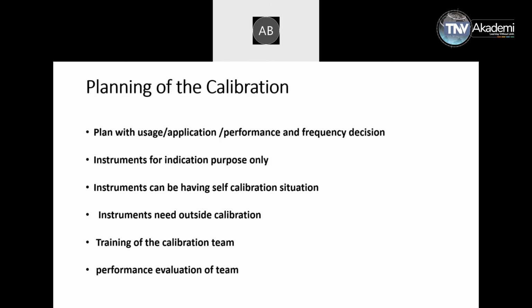There are some instruments for which in-house calibration is not possible, or the manufacturing unit, assembly unit, or service industry does not have the facility to calibrate inside the organization. So these instruments, equipments and machines are sent to outside agencies which have traceability to national or international standards for calibration. And our purchase department is again important in that.